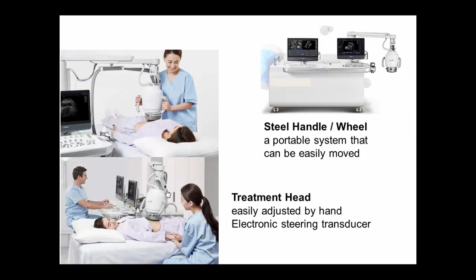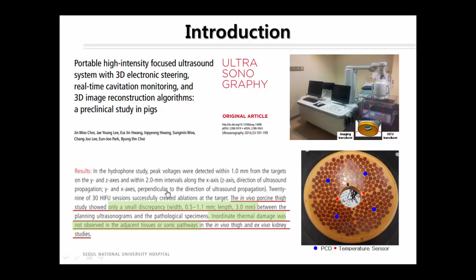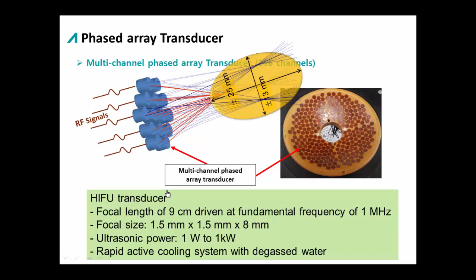a 256 phased array channel transducer. Red spots indicate temperature sensors that measure the temperature of the surrounding degassed water. Blue spots indicate passive cavitation detection sensors. This HIFU transducer has a focal length of 9 centimeters, driven at a fundamental frequency of 1 megahertz. Focal size is 1.5 millimeters by 1.5 millimeters by 8 millimeters. Ultrasound power ranges from 1 watt to 1 kilowatt. To prevent skin burn, it has a rapid active cooling system with degassed water. Using electronic steering like this, it provides a 3D targetable zone with an axial diameter of plus or minus 25 millimeters and a lateral diameter of plus or minus 13 millimeters.